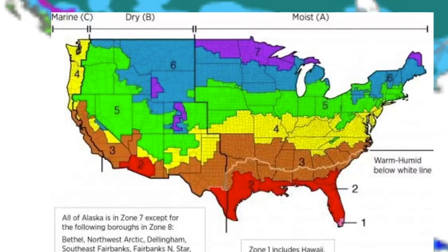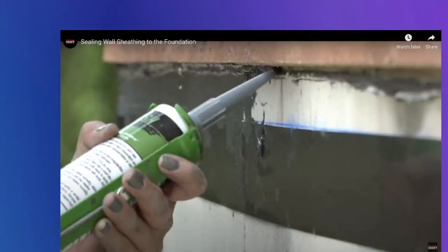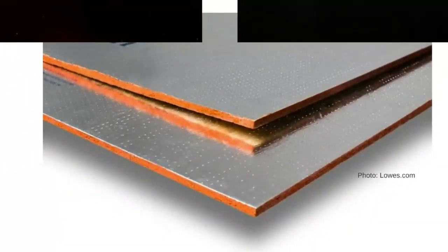In colder climates, heat flow reductions are typically done by specifying higher R values of insulation and higher air tightness values to minimize both the largest sources of conduction and convection heat loss. Windows are predominantly important for heat loss in cold climates, whereas in hot climates, they're the main source of heat gain. So they sabotage boilers in the north and AC units in the south. In the warmer, more southern climate, solar control is typically the key to thermal control and comfort. Air tightness is important, but as a generalization, air tightness is not as critical, and the R value levels do not need to be as high to maintain interior comfort. Radiant barriers in the roof assembly, shading, and low-E coatings on windows is how radiant heat flow is slowed.